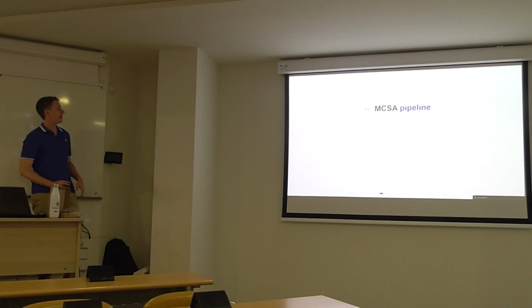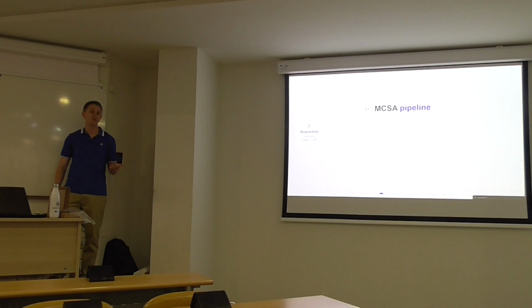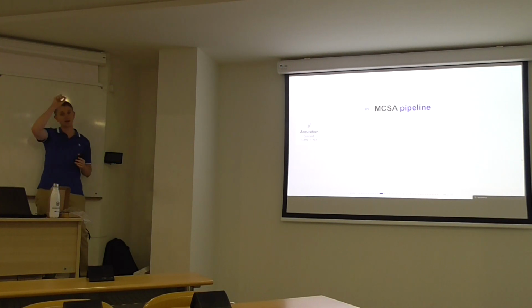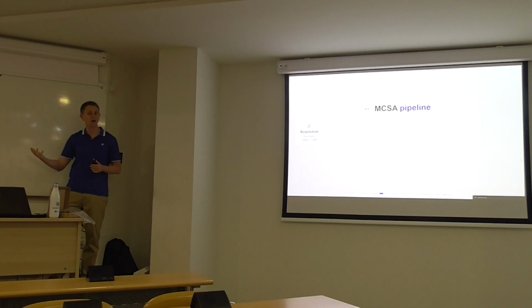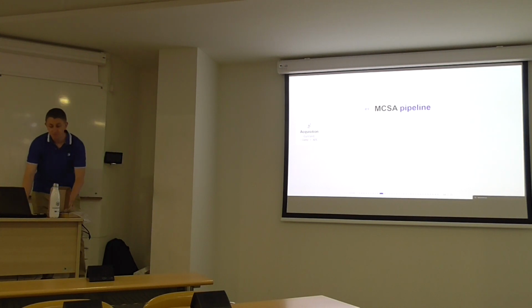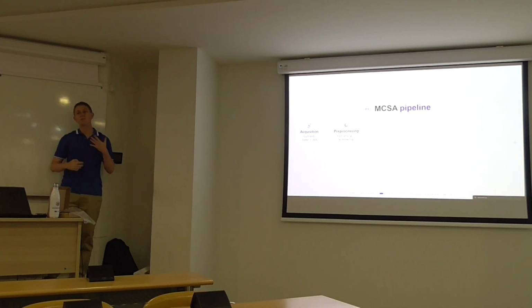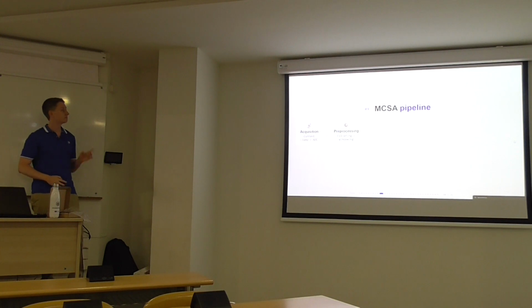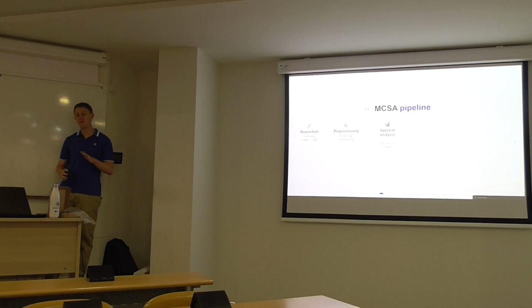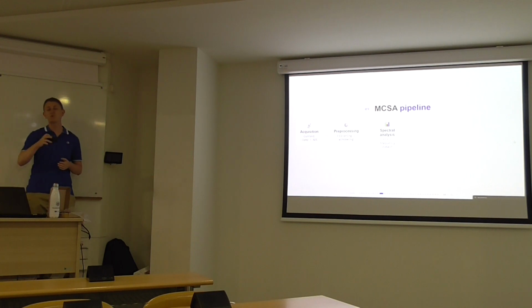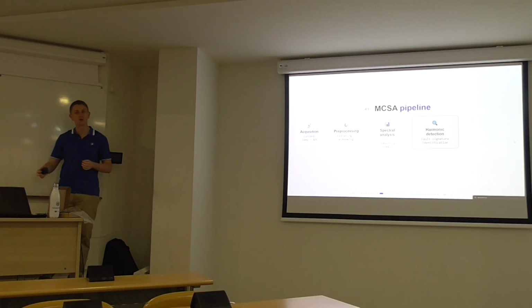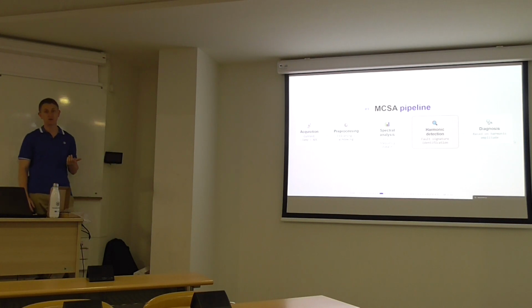Well, so what is the pipeline in the MCSA process? First of all, we need to acquire the signal. We have a continuous analog signal that we need to transfer into a digital one to analyze it. For that we need the current clamp and an ADC, an analog to digital converter. Then we need to apply some preprocessing, filtering, windowing. Then the spectral analysis, we apply the FFT and obtain the frequency domain. And once we have the frequency domain, we have to perform the harmonic detection, that is, to identify the fault signature. Once we have the fault signature, we can compute its amplitude and provide a diagnosis.